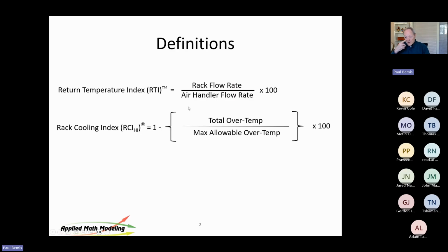There's another one as well called the rack cooling index. This is a little more subtle. This is how many hotspots do I have, and is it a problem? You can think of it that way. This is 1 minus the over temp regions on the rack inlets. We're talking about rack inlets here only, divided by the allowable over temp times 100.